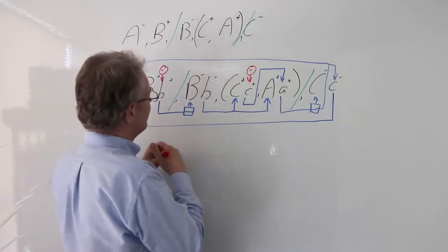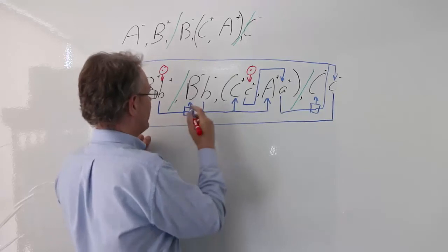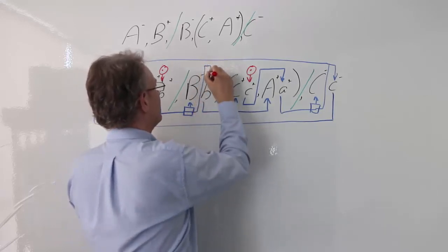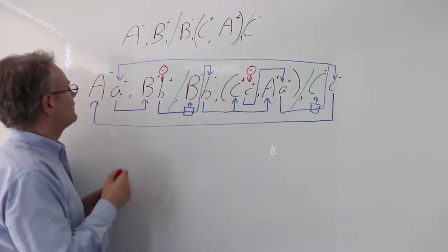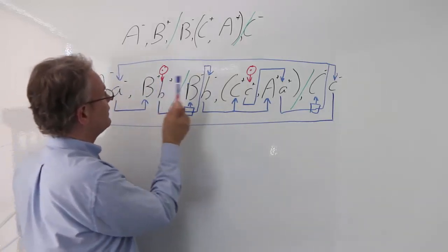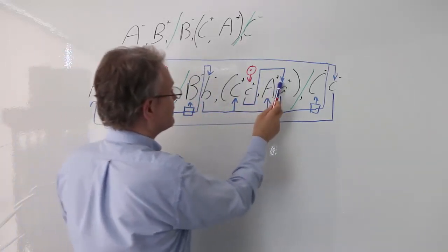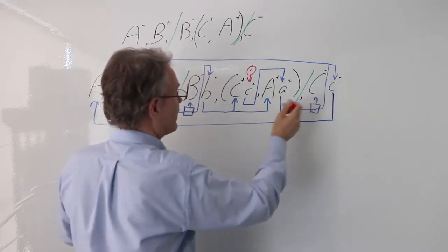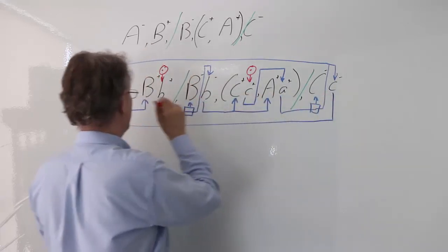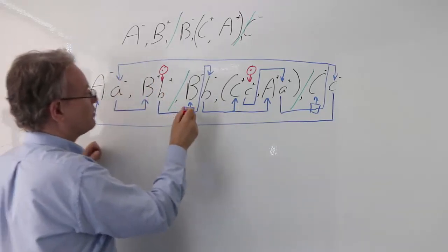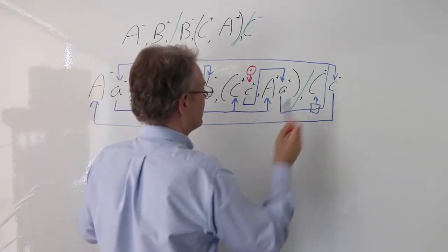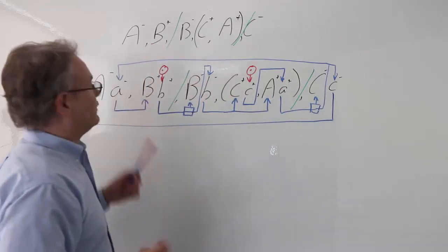The only thing that I've got missing is that this guy doesn't have air, and he gets air from the relay valve. So again, do all of my limit valves have air going down? Yes, yes, yes, yes, yes, yes. Do all of my actions have air going up? Yes, yes, yes, yes, yes, yes. Does the air coming out of here go to a yes? And goes to a relay valve? Yes, it does. I'm done.